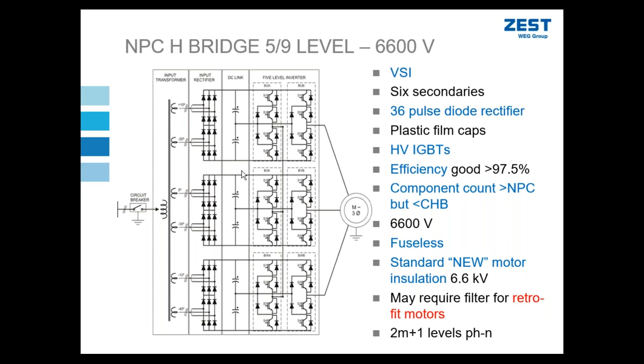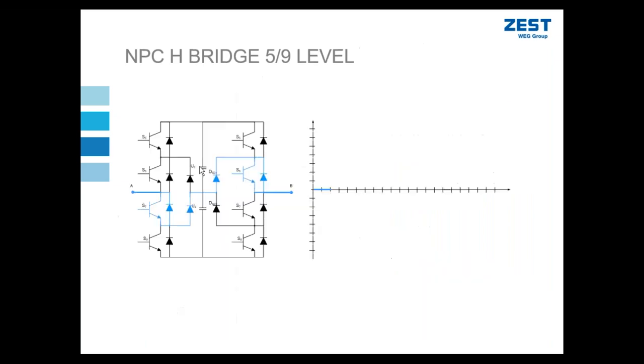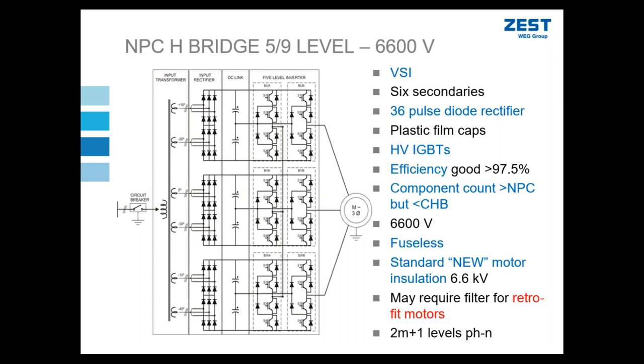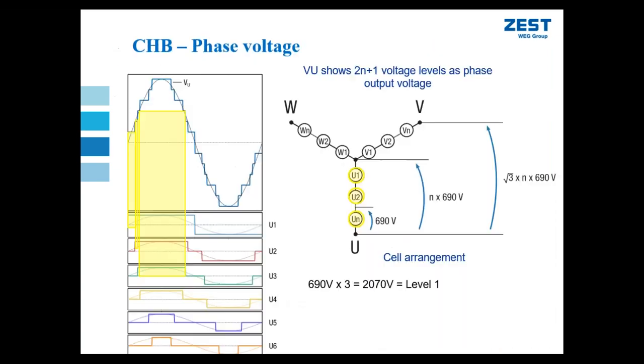What was the other part of the question about reactors? So reactors are devices that are applied. They are basically an inductive core similar to the core of a transformer. It's normally a laminated core that's covered in copper winding with multiple turns. And these are put in series at the input of low voltage VSDs to dampen the voltage peaks. And as a natural consequence, they also dampen the distorted current waveforms. So let me try and demonstrate how that works. I don't have that specific info in this presentation, but let me show you how it works basically. I'm going to take you all the way back to those current waveforms that were distorted right in the beginning.